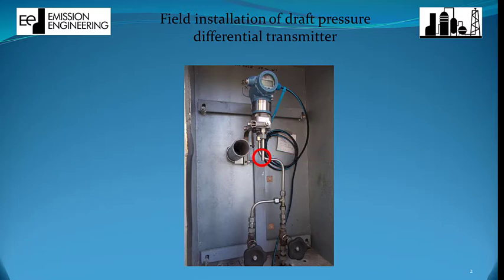Let's assume the cabinet is open, wind that passes by will affect the transmitter signal, as wind changes the pressure conditions around this tubing. This can also happen if the cabinet is closed and the tubing end is located outside of it, as often seen in refineries.